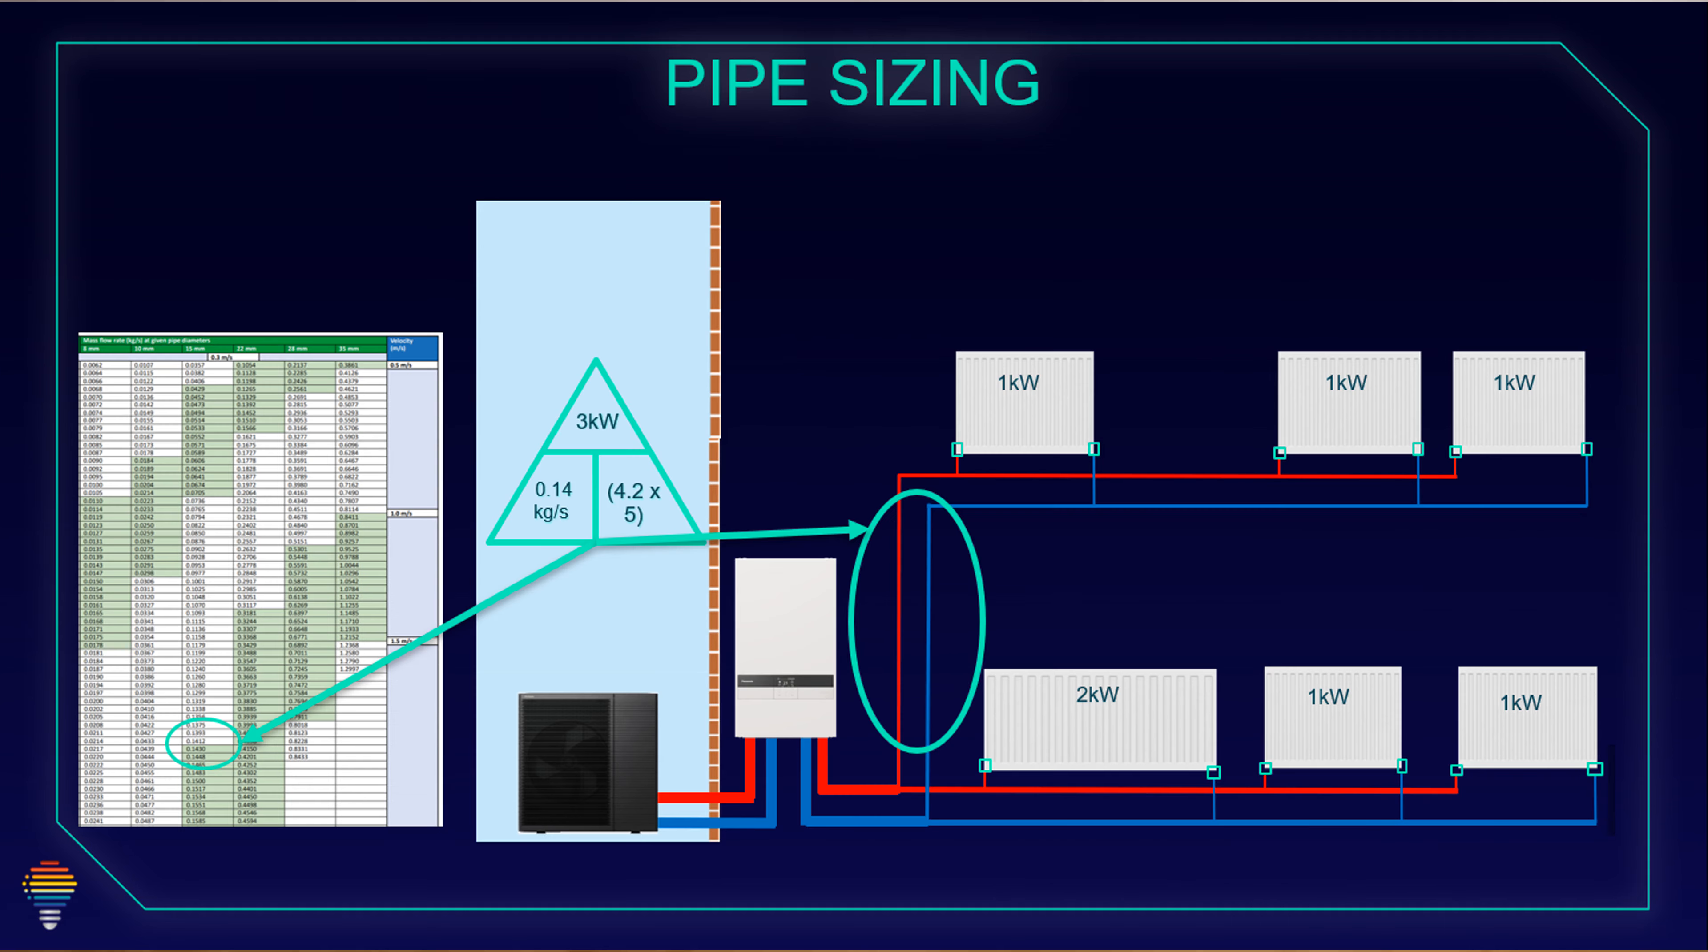And if we are going on one side with 3 kilowatts, so we have 3 radiators of 1 kilowatt. For these 3 kilowatts, our flow rate is 0.14 kilogram per second. And for delta T 5, if we enter the table, we see that we can go with 15 millimeters.